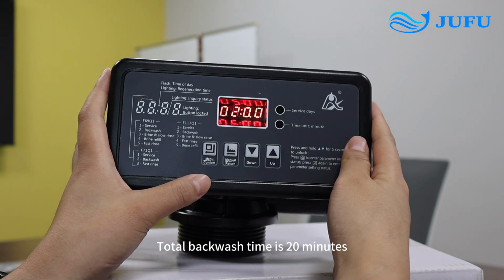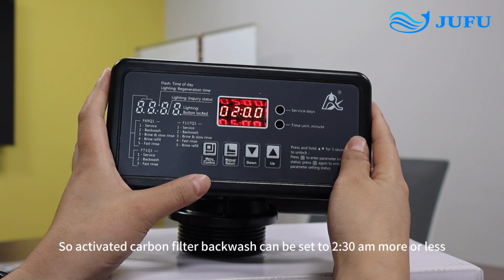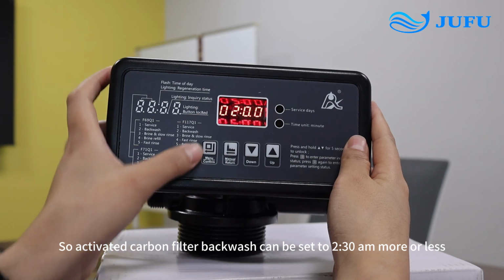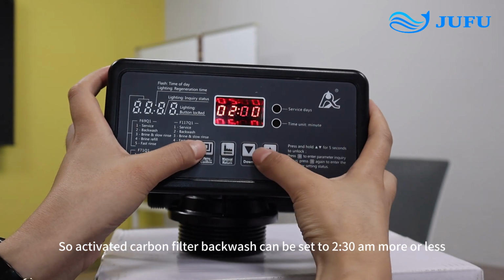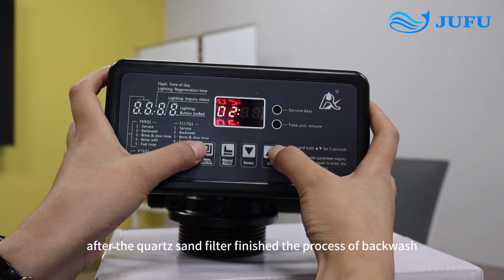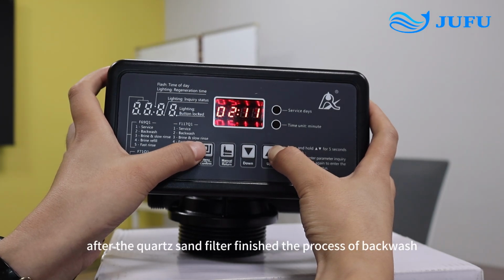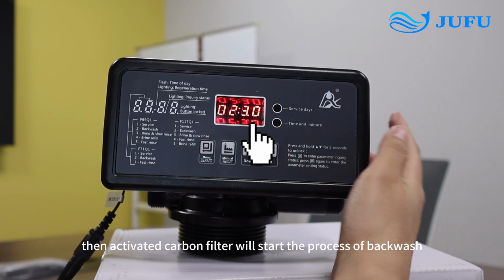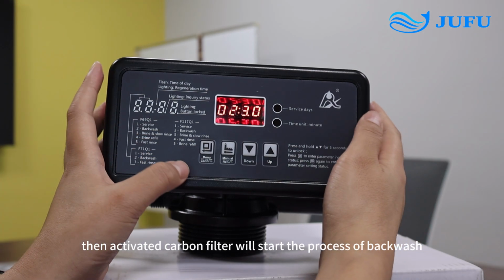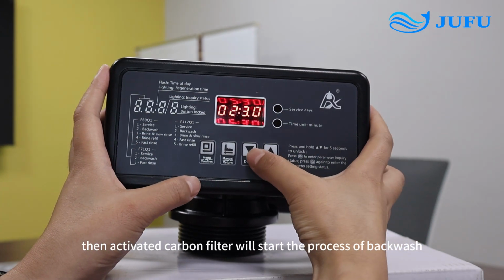Total backwash time is 20 minutes. So activated carbon filter backwash can be set to 2:30 a.m. more or less. So just after the quartz sand filter has finished the process of backwash, the activated carbon filter will start the process of backwash.